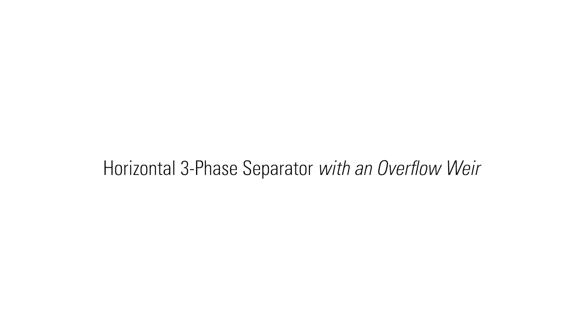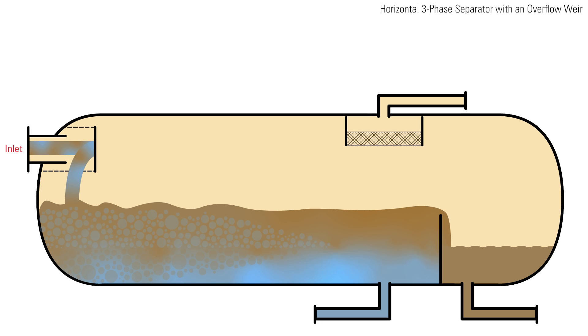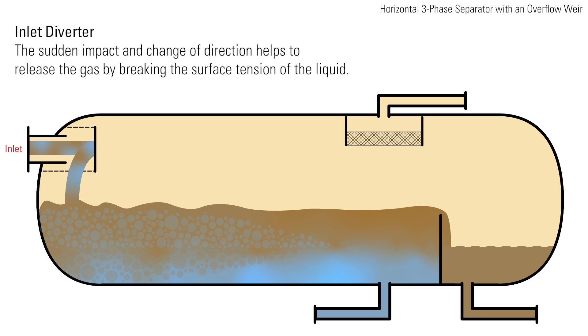In a horizontal three-phase separator with an overflow weir, fluid enters the vessel through an inlet and immediately hits an inlet diverter. This sudden impact and change of direction helps to release the gas by breaking the surface tension of the liquid.